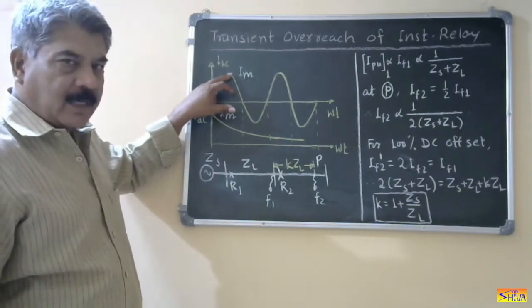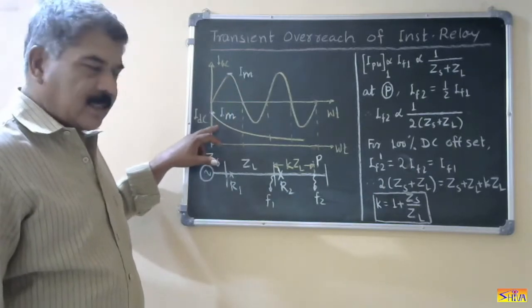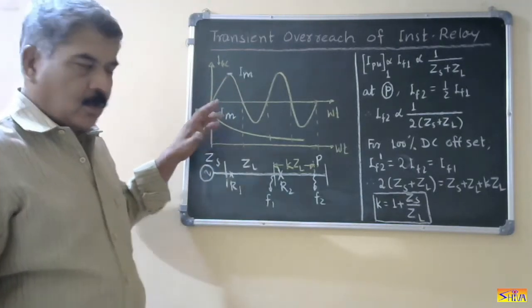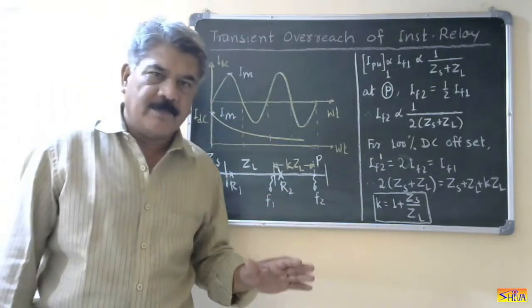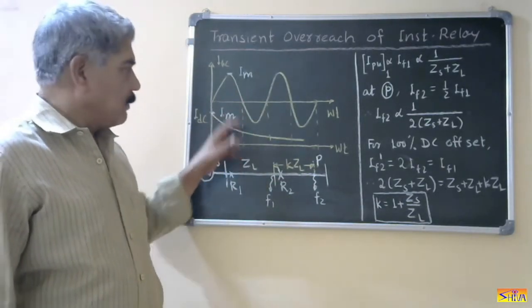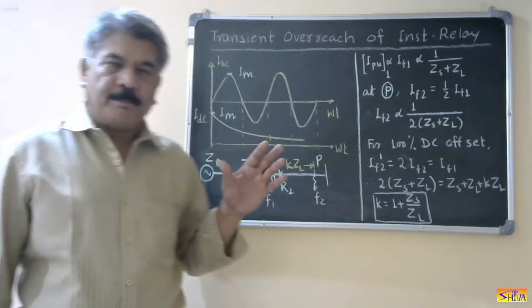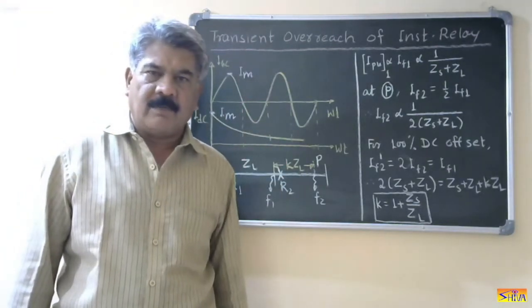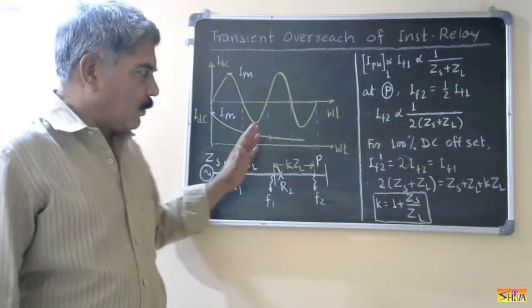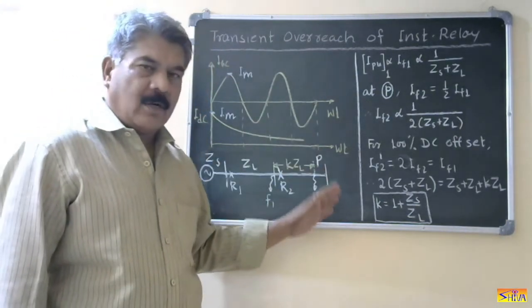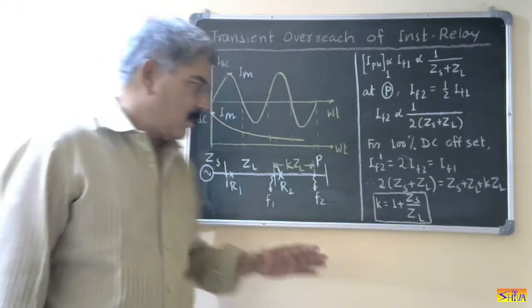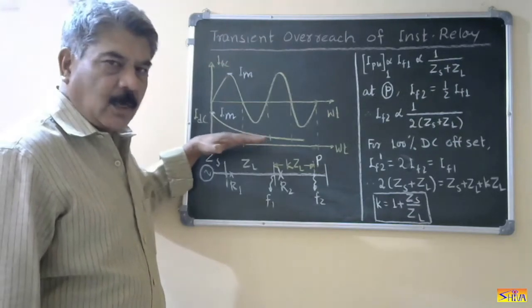In the worst case, the peak value of the DC offset can go up to IM, the peak value of the sinusoidal component. If we consider the worst condition, these two will be superimposed, so the maximum value of the fault current will be equal to 2 times IM. For derivation, we always consider the worst condition. That is about the DC offset of the fault current.